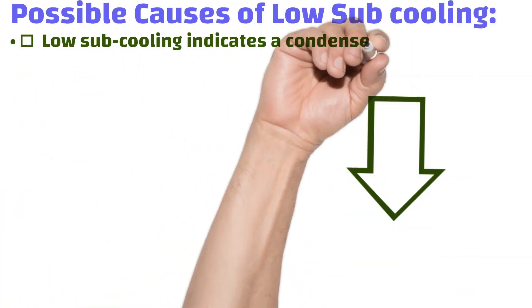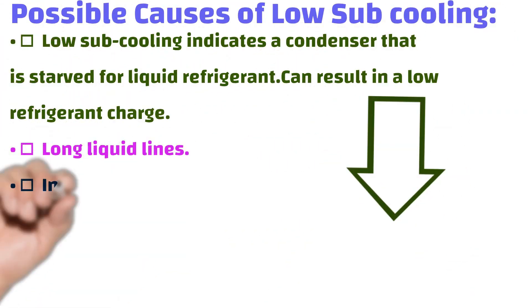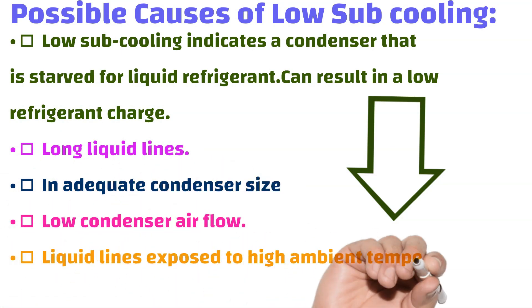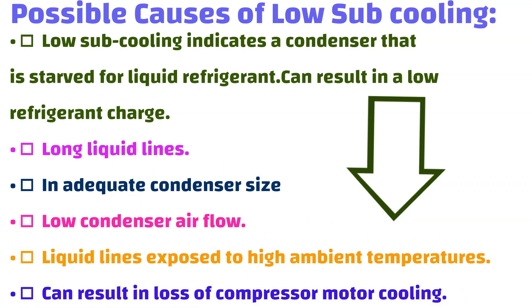Possible causes of low sub-cooling: one, low sub-cooling indicates a condenser starved for liquid refrigerant, which can result in a low refrigerant charge; two, long liquid lines; three, inadequate condenser size; four, low condenser airflow; five, liquid lines exposed to high ambient temperatures; six, can result in loss of compressor motor cooling.